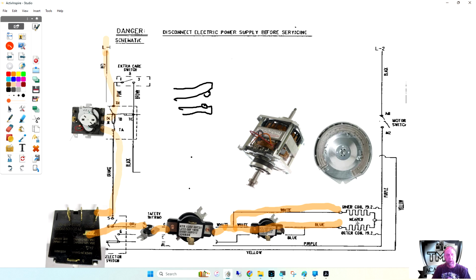Why am I going through a separate thermostat on one and then the other? There's 2 coils on the heater. The upper coil is going to be controlled by this thermostat, and the lower coil is going to be controlled by this one. Most likely this thermostat's temperature setting is lower than that one, because if this one shuts off, they both shut off.